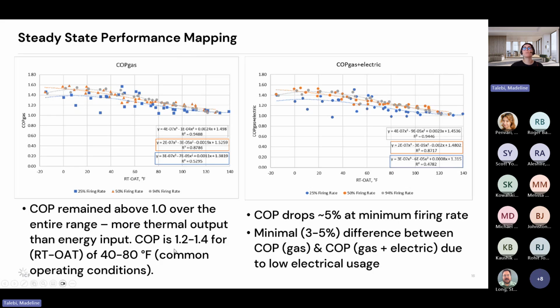And then the COP is about 1.2 to 1.4 for return temperature, outdoor air temperature, normalizing factor of 40 to 80 degrees Fahrenheit. So those are typical common operating conditions. That was a positive finding. In this case, we want to optimize the COP as much as possible. That's going to reflect how efficient our unit is and how optimally it's been configured. For comparison purposes, we see the COP gas plus electric. We see that the COP does drop about 5% at that minimum firing rate. And it was minimal, about a 3 to 5% difference between the COP gas and the COP gas plus electric. Again, this is attributed to the low electrical usage that's required for the unit.